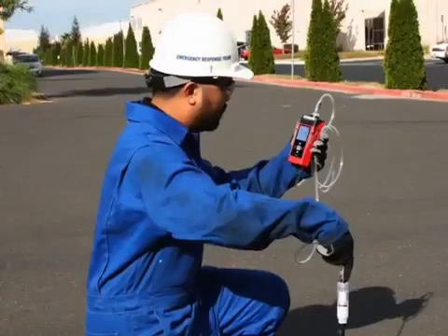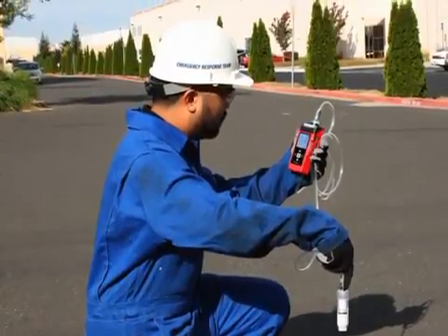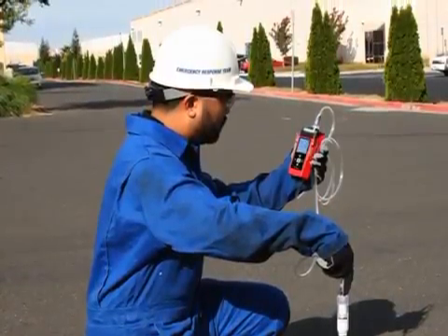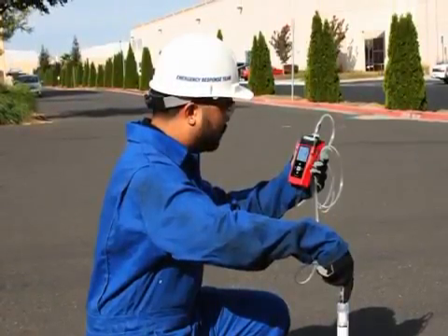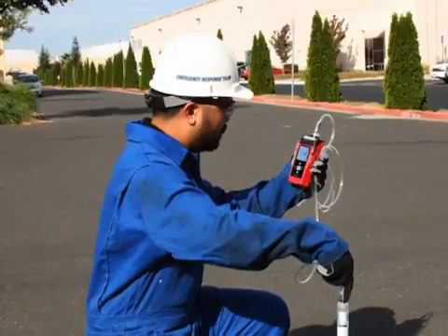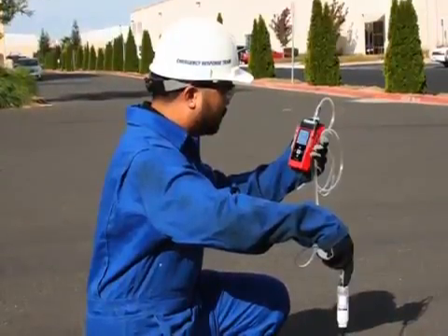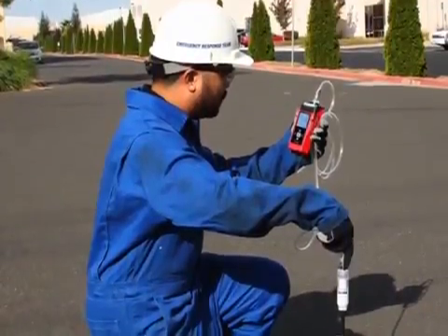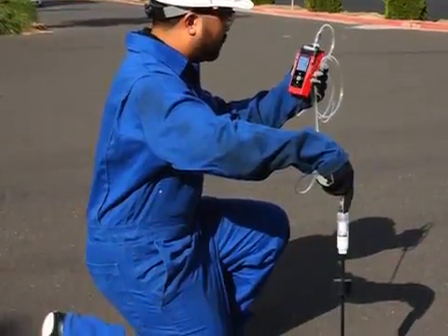Bar hole mode is used to perform consistent checks of bar holes when tracking down underground gas leaks. When the gas tracer is in bar hole mode, only the combustible and oxygen channels are displayed. If a gas tracer is intended for bar hole testing, it is shipped with bar hole mode enabled so that the operator must choose which operational mode to use when the unit is turned on.